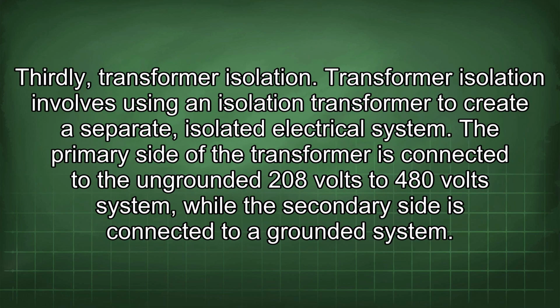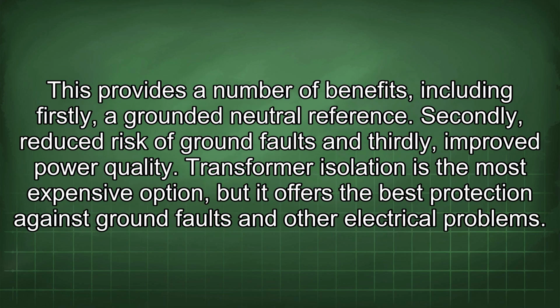Thirdly, transformer isolation. Transformer isolation involves using an isolation transformer to create a separate, isolated electrical system. The primary side of the transformer is connected to the ungrounded 208 volts to 480 volts system, while the secondary side is connected to a grounded system. This provides a number of benefits, including firstly, a grounded neutral reference. Secondly, reduced risk of ground faults, and thirdly, improved power quality.